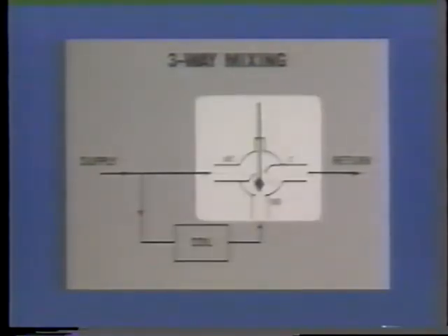This valve has the capability of going to full flow in either direction, but generally mixes or modulates the flow. It is designed to mix the two inlet ports, modulating the flow through the coil.